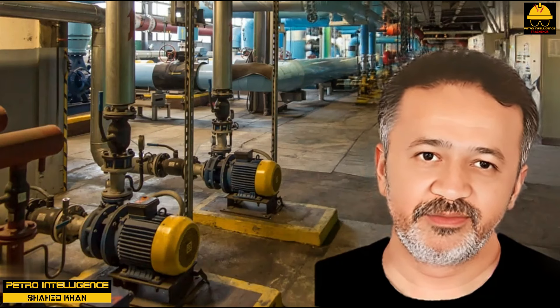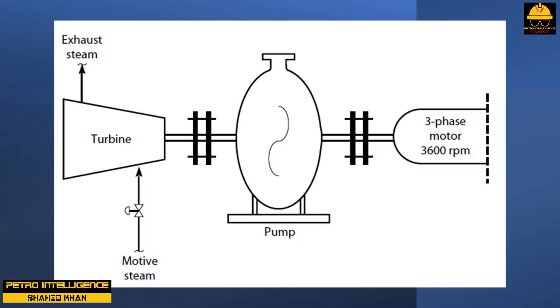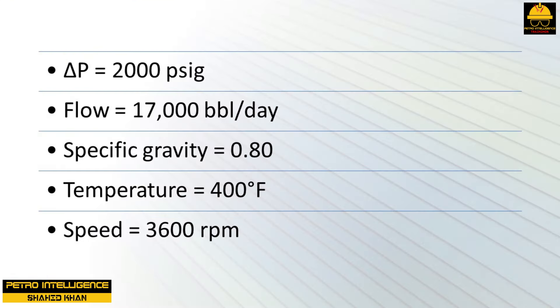This picture is a sketch of a centrifugal pump driven by a three-phase motor with a turbine helper. This particular pump was charging a light gas oil stream to a high-pressure hydrocracker. The pump was operating quite close to its design conditions: delta P equals 2000 psig, flow equals 17,000 barrels per day, specific gravity equals 0.80, temperature equals 400°F, speed equals 3600 RPM.